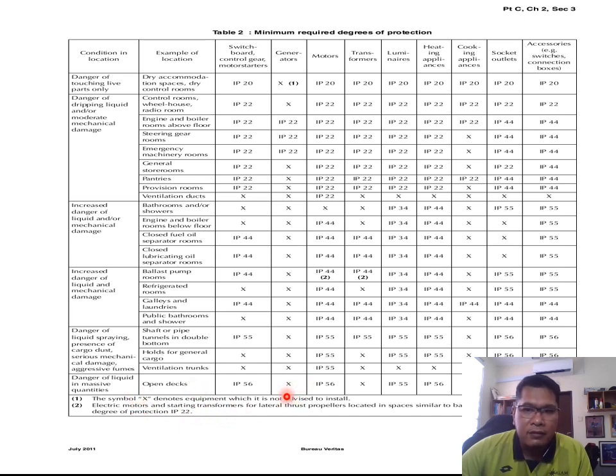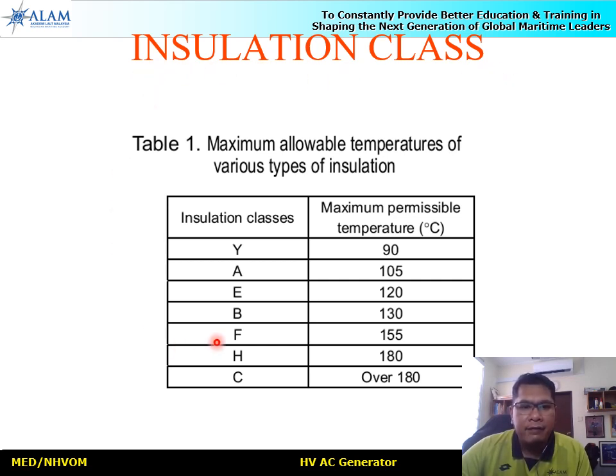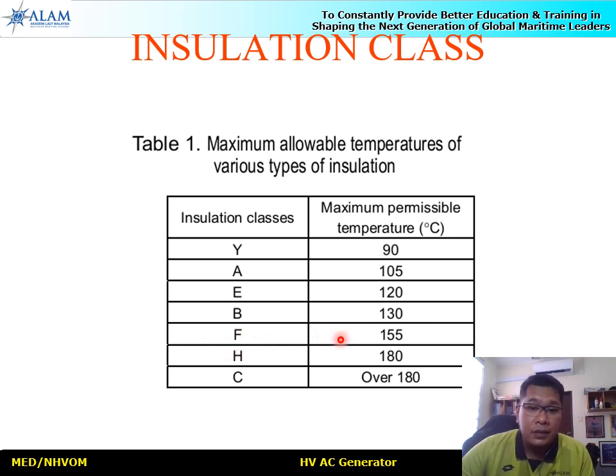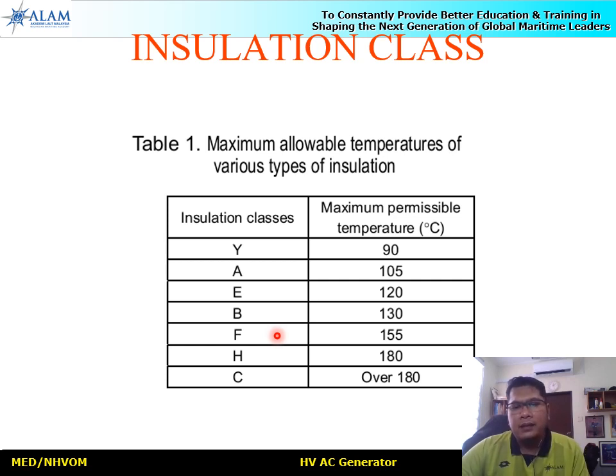From the specs, both generators have insulation class F. The insulation class table shows maximum allowable temperatures for various insulation types; Class F allows a maximum permissible temperature of 155°C. Since both generators share the same class, their operating temperatures are essentially the same. On board ships, the alarm limit for high winding temperature — for either low or high voltage generators — is typically around 80 to 90°C.